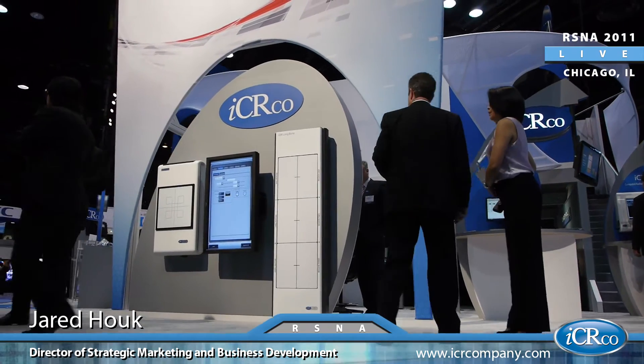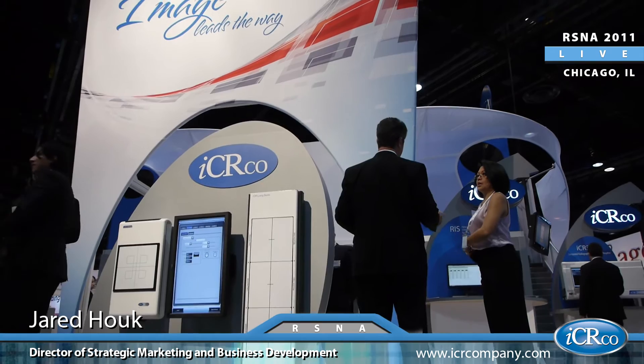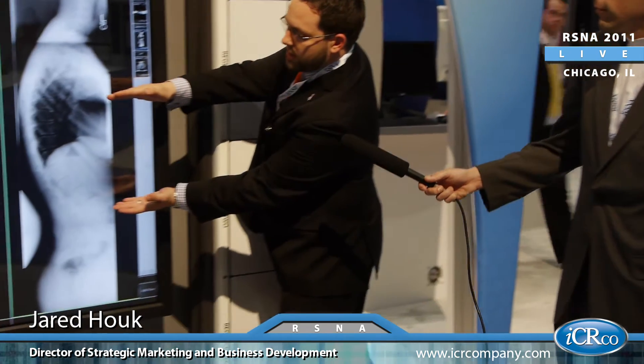A lot of times with customers such as pediatric or orthopedic doctors, they're going to be looking to take a full spine image. To acquire this image, typically a DR panel is going to require you to take three separate images or three separate radiographs and then stitch them together. Now the IDR Longbone is unique in the fact that you can do this with a single exposure.